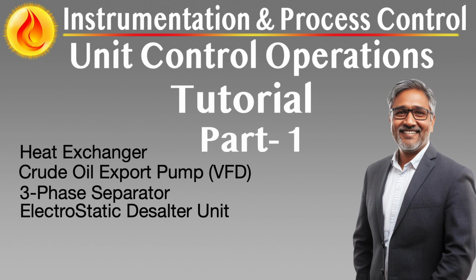Oil and water levels are typically managed via cascade control structures. For example, the interface level controller for water may set a flow set point for a water dump valve controller, while the oil level controller governs the oil outlet valve. This approach decouples the fast-acting valve response from the slower-moving level signal, improving stability.